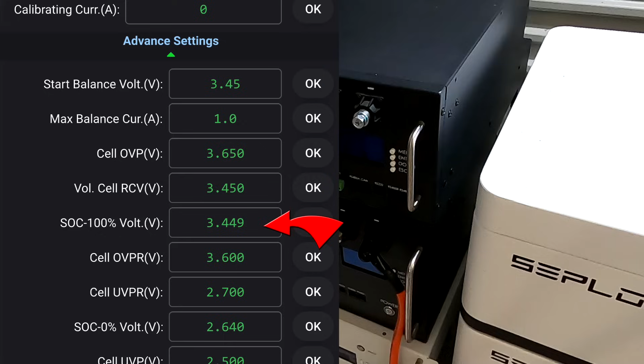The JK BMS takes this times 16 and reports it to the inverter. We've got a state of charge 100% voltage of 3.449, so this needs to be under the requested charge voltage. I have already requested a change for that - it's not good enough, but for the moment it works. It's not optimal, but it works.